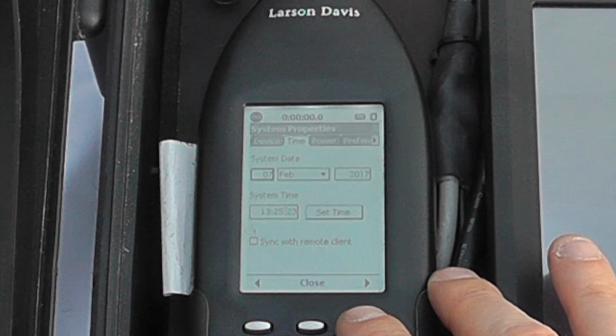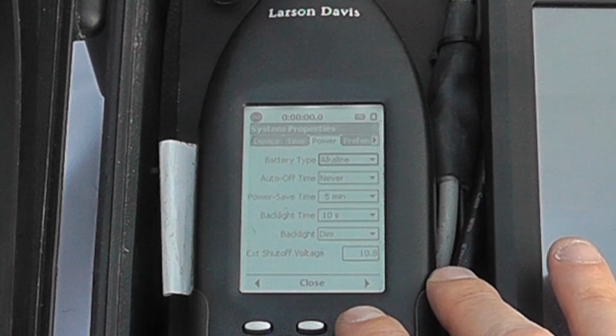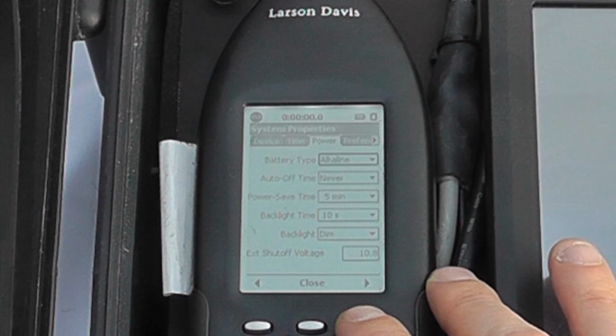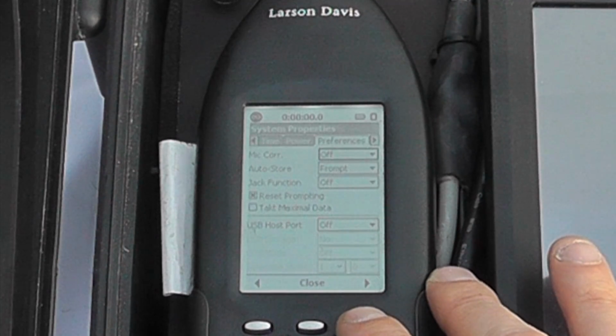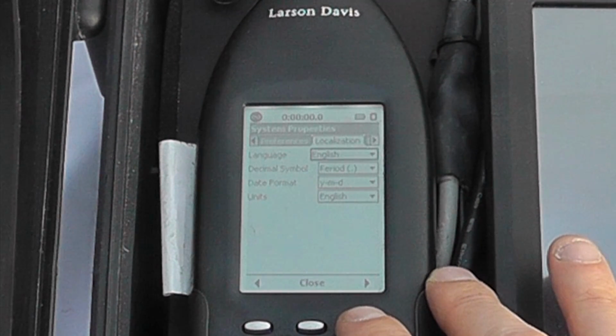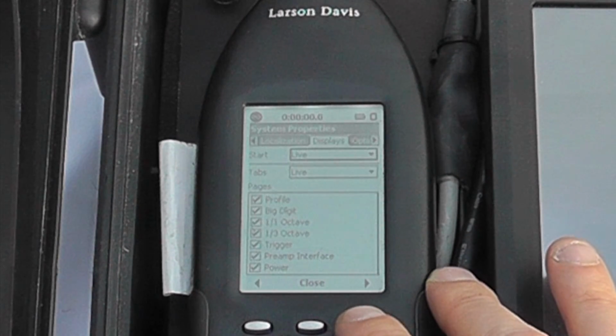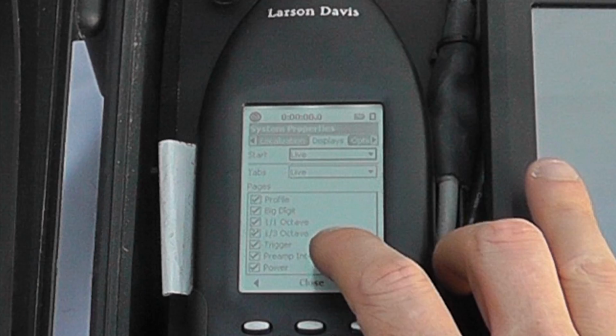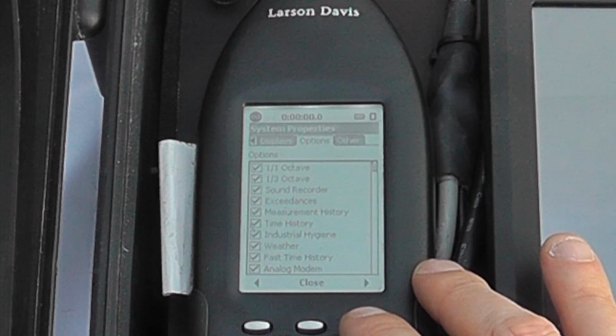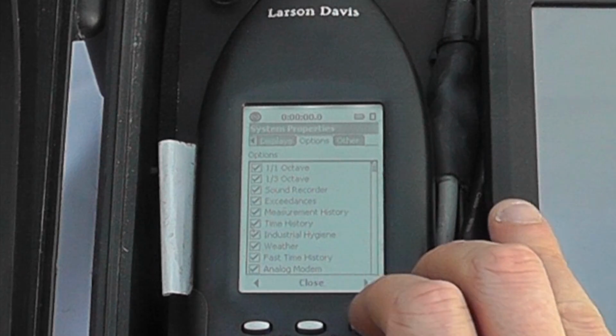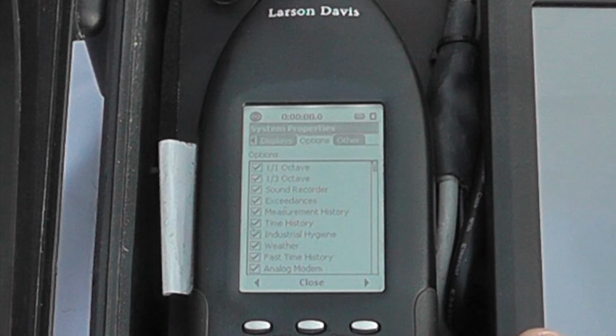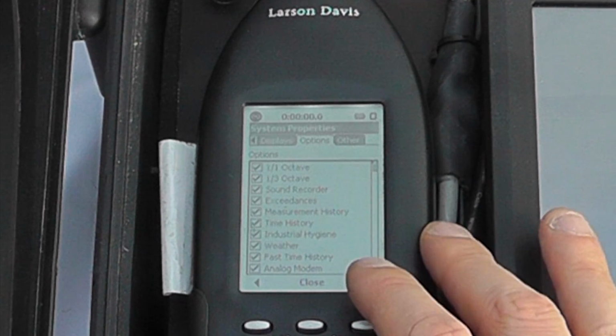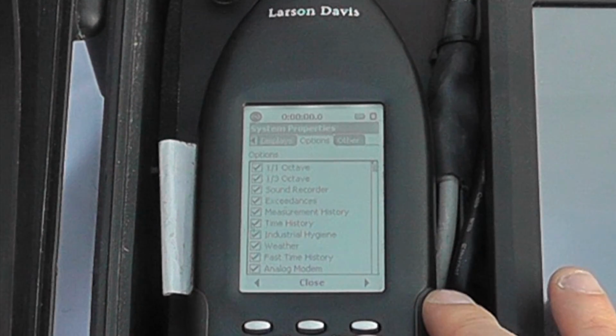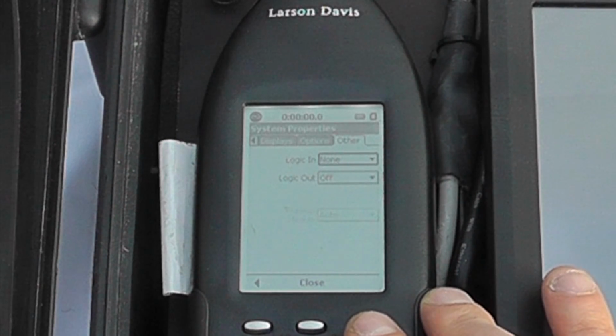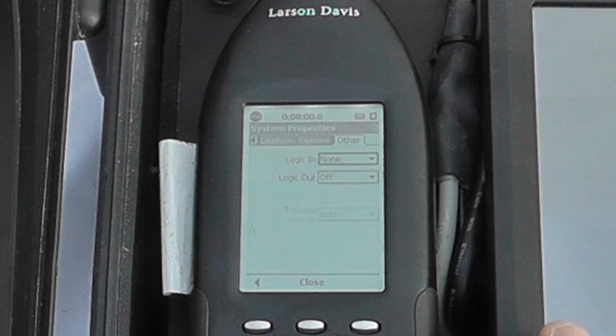We can look at the system properties in terms of any instrument identifiers, time and date stamps on the instrument, the power, whether it's running off alkaline or battery backups, any auto off times we have enabled, any preferences in terms of mic corrections, etc. Localization, so what language, dates, formats we're using, the displays we have, so what profiles we're using, whether we're using octaves or third octaves, and any trigger information, what options are enabled on the device at the moment. So this happens to be a fully loaded 831, so includes all the octave band data, third octave, sound recorders, exceedances, etc. And then any of our logic gates for the bottom of the instrument.